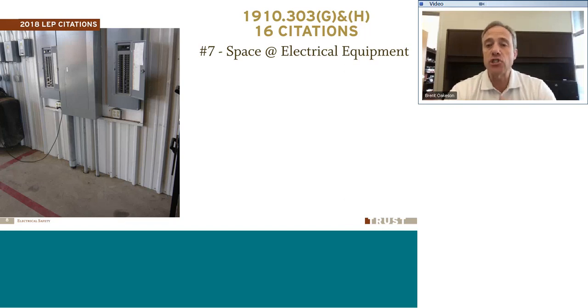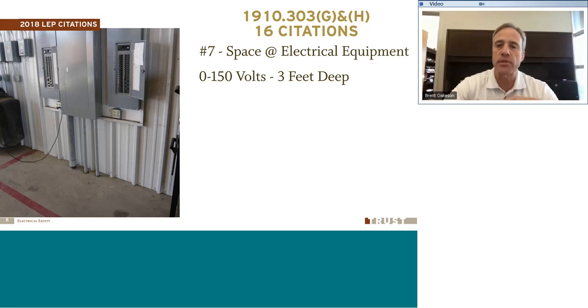And then as a general rule, it needs to be about a 3-foot space to the front of those electrical panels, and those spaces have to be kept clear. The door on the electrical panel has to be able to open at least 90 degrees, and we need to have that clear space with nothing stacked in front of these panels. And that includes things that may not be all the way up blocking the door of the panel, but they're on the ground in front of the panel, where they could be a trip hazard or maybe even a fire hazard, being right close to that panel or in front of that panel. So this floor in front of these panels needs to be kept perfectly clear.